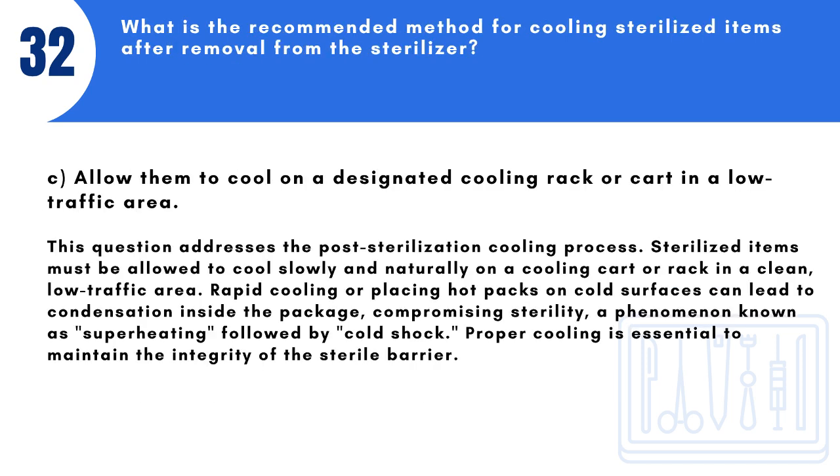Answer: C. Allow them to cool on a designated cooling rack or cart in a low-traffic area. This question addresses the post-sterilization cooling process. Sterilized items must be allowed to cool slowly and naturally on a cooling cart or rack in a clean, low traffic area. Rapid cooling or placing hot packs on cold surfaces can lead to condensation inside the package, compromising sterility, a phenomenon known as superheating followed by cold shock. Proper cooling is essential to maintain the integrity of the sterile barrier.